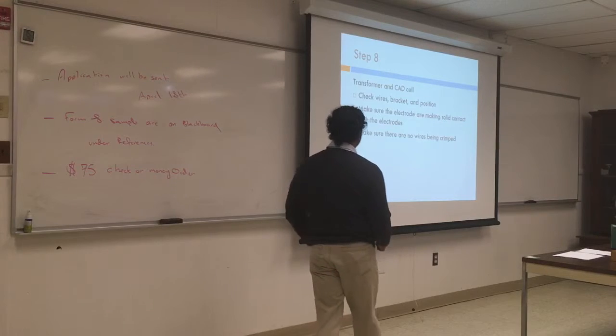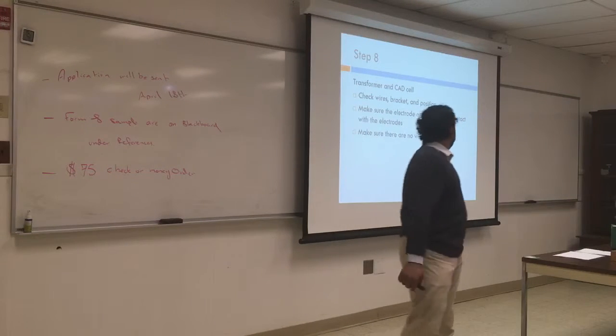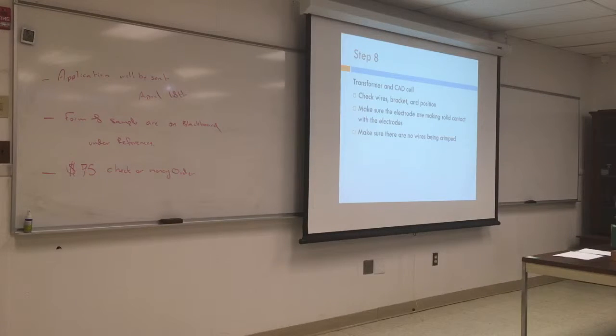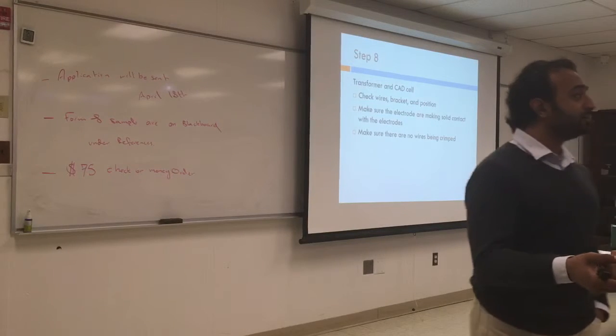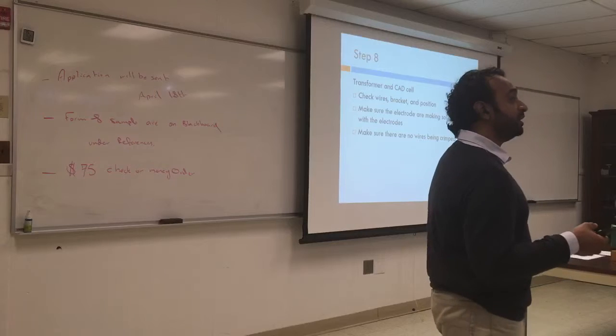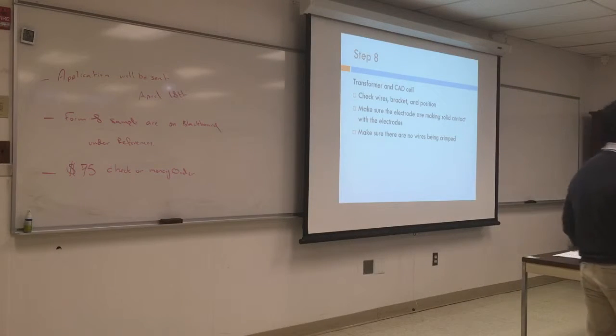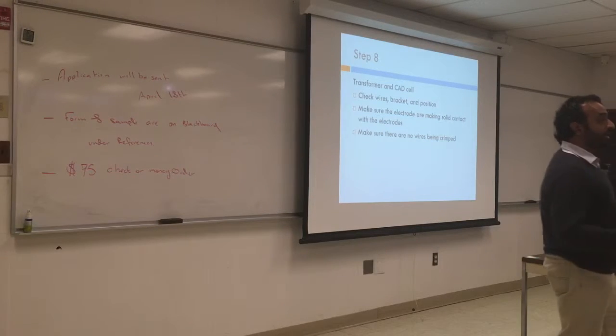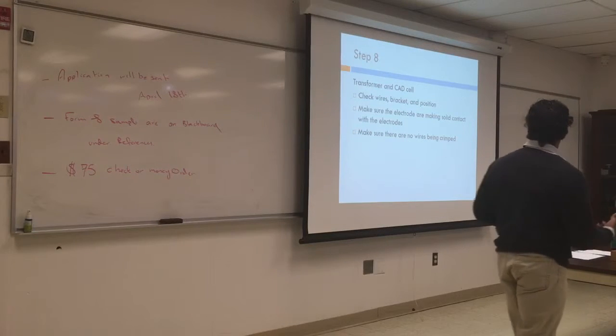So step 8, we will check the transformer and the CAD cell. Check the wires, the brackets, and the position of the transformer and the CAD cell. Make sure they are in the right location. We've seen that already when we did the maintenance on those oil burners. The CAD cell is not very sturdy. It's shaking. Somebody put it in there without a screw. That's not correct. Make sure it's secure in place. The CAD cell eye always follows the receptacle. A lot of times they have a very loose connection, and that's not the way to put it, because sometimes when you put the cover down, the air flow will dislodge it. So make sure it's in the right place and fastened properly.